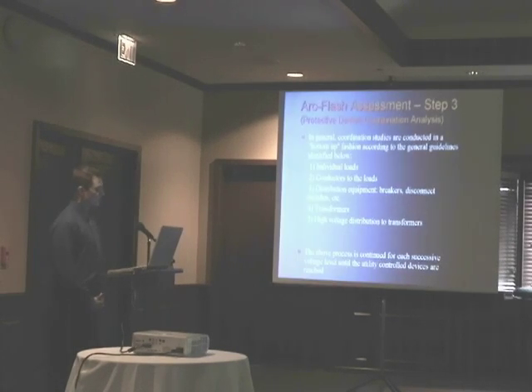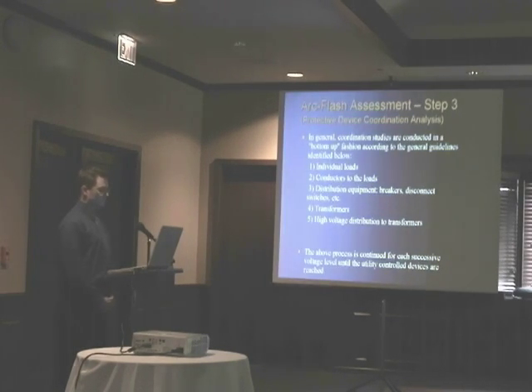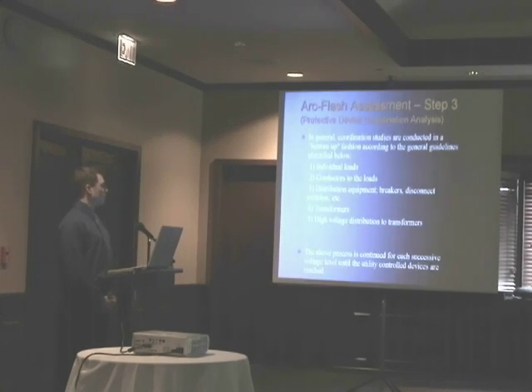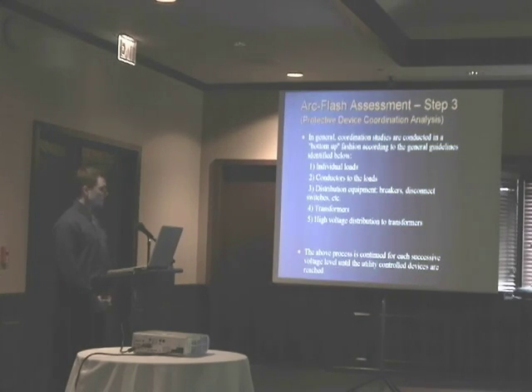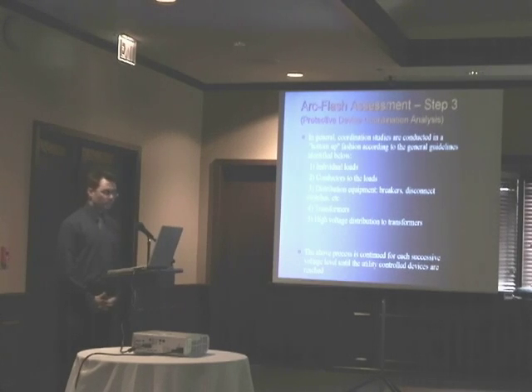In general, coordination studies are conducted in a bottom-up fashion, according to the general guidelines identified below. Like I said, we're going to start with individual loads, then go to conductors to loads, distribution equipment such as breakers and disconnect switches, and then transformers.